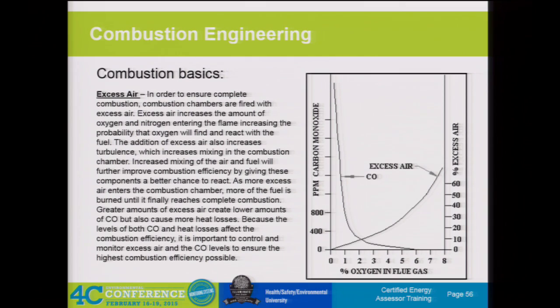This is the classic curve that you've probably seen—with the relationship of, as you supply more excess air into a system, you're driving down the products of incomplete combustion, your carbon monoxide. This is fuel dependent—different fuels require different amounts of excess air. Natural gas requires a lower excess air concentration. When you're looking at coal or other solid fuels, you usually have to run a higher excess air content. So this profile is somewhat system and fuel dependent, but in general, the relationship is the same. The more excess air you're putting into the system, the more chance to get to complete or stoichiometric combustion. Zero is the point where your air flow is ideal for the fuel input, and then additional air is needed to overcome inefficiencies in the system.